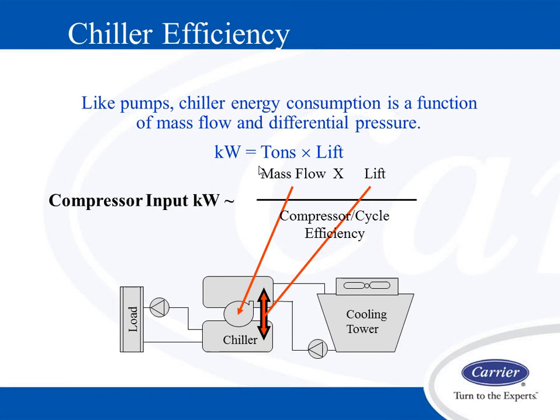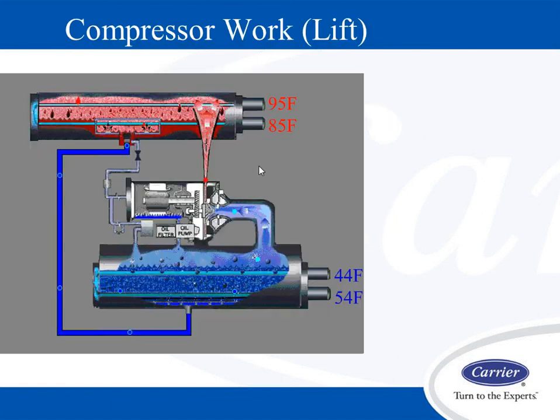So let's talk about chiller efficiency, and we'll go into this whole IPLV. Even though we have the best IPLV in the marketplace, in my opinion I feel it's a trap, and it's not the correct way to properly measure the efficiency of a chiller. Compressor input kW is equal to mass flow, refrigerant flow, times lift, divided by the cycle efficiency. So really what we look at is kW equals tons times lift.